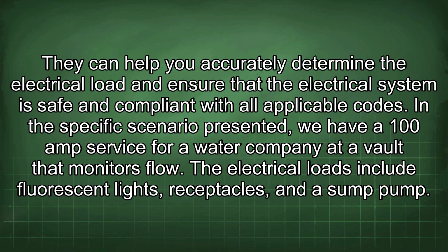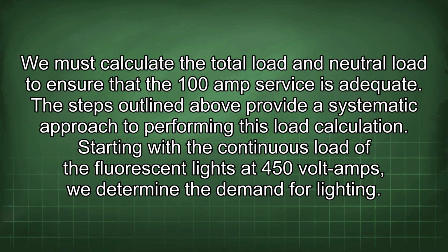with all applicable codes. In the specific scenario presented, we have a 100 amp service for a water company at a vault that monitors flow. The electrical loads include fluorescent lights, receptacles, and a sump pump. We must calculate the total load and neutral load to ensure that the 100 amp service is adequate. The steps outlined above provide a systematic approach to performing this load calculation.